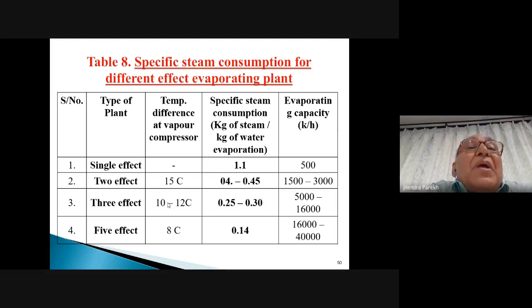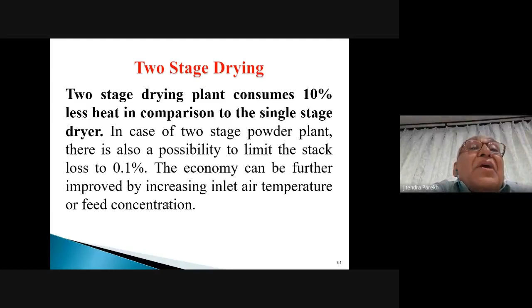Now, a two-stage drying plant consumes 10% less heat in comparison to a single stage dryer. In a two-stage drying plant, there is also the possibility to limit the stack losses to 0.1%. You can reduce the stack loss once you have a two-stage dryer. The economy can be further improved by increasing the inlet air temperature or the feed concentration. So the capacity of the two-stage dryer can also be increased, and the stack losses reduced. Next, please.